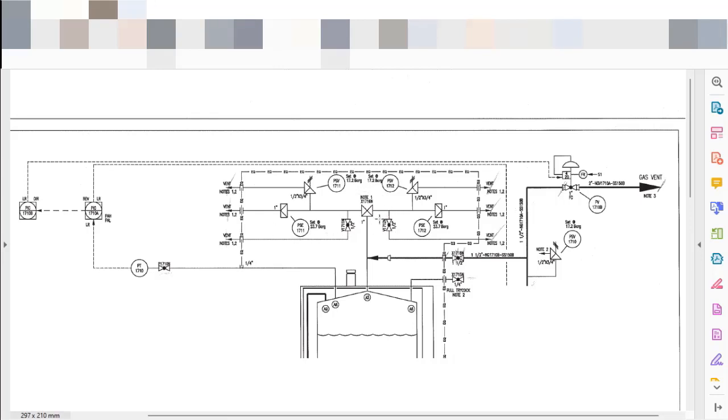And just to finish this example, I have here a diverter valve that is responsible for always leaving a set of relief devices available to relieve the pressure. My diverter valve will be aligned to the left side of my set, or aligned to the right side of my set, where I have the safety valve, the rupture disc, and also a vent valve. Why do I have this vent valve? Eventually, I will need to do maintenance of the safety valve and also of the rupture disc.